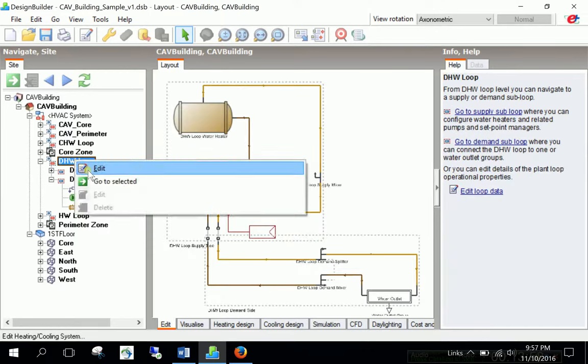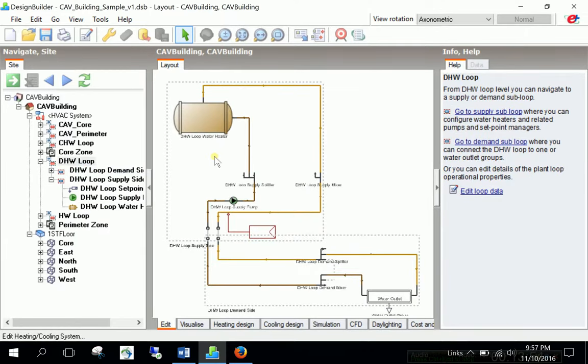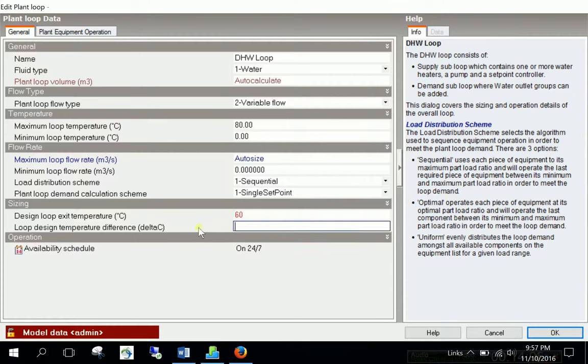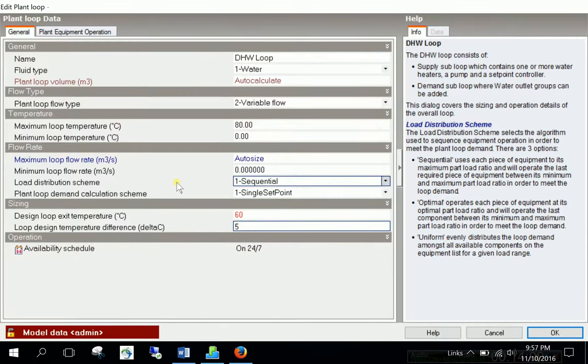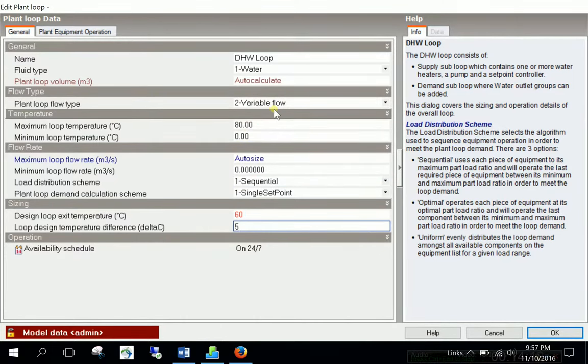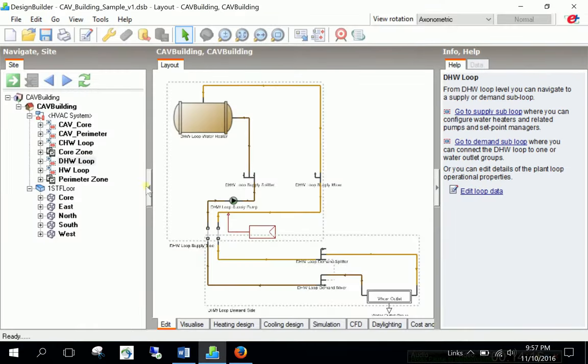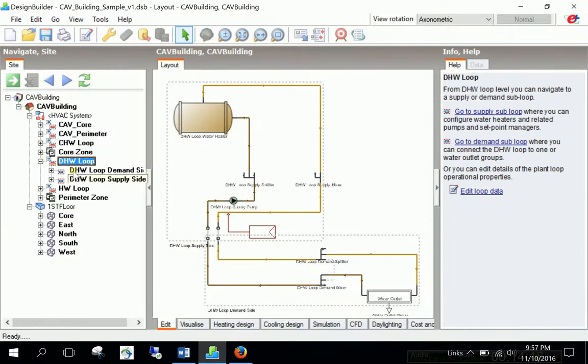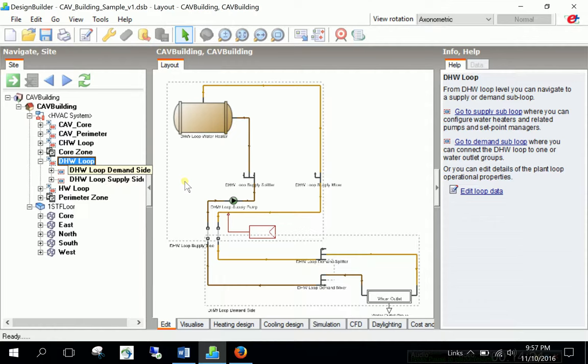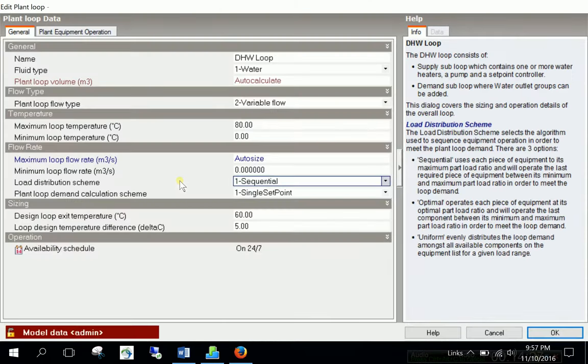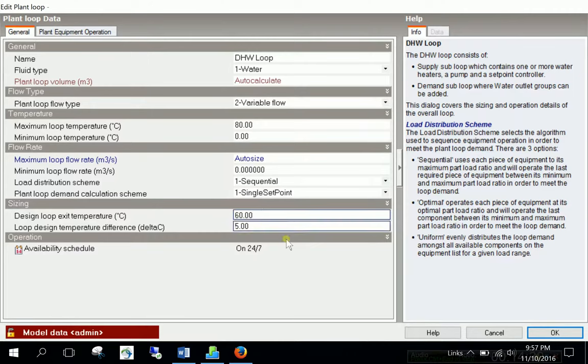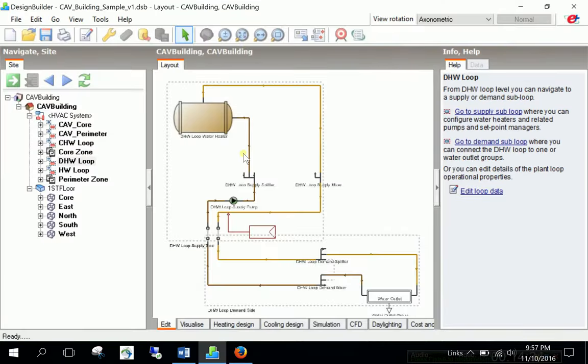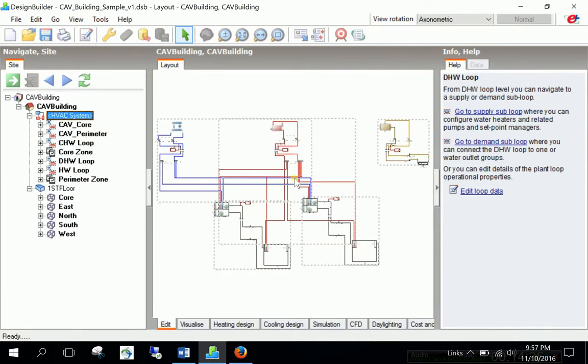In the loop. Right click. The domestic hot water loop. Is there any properties. It's waiting a little bit. You can change the sizing design to 60 exit temperature. To be sure. And 5 degree difference. Exit temperature. Just to be on the same safe side. Plant loop flow rate is variable flow. Say okay. I think. It should be quick. It may be quick. But how did I do it. I stayed on the DHW loop. I right click. I press edit. And then. Wait a little bit. And then see the results. And change this exit temperature. And the temperature difference. Say okay. Wait. Now these are the settings. And I am checking again. Am I forgetting something? No. It was quicker. Because of the fact that we don't have any condenser and condenser loop. And the pump. And stuff like that. So we don't have it. So it's faster.